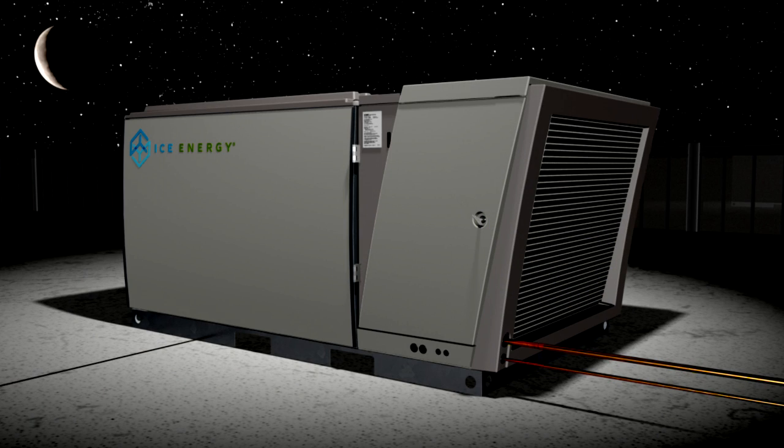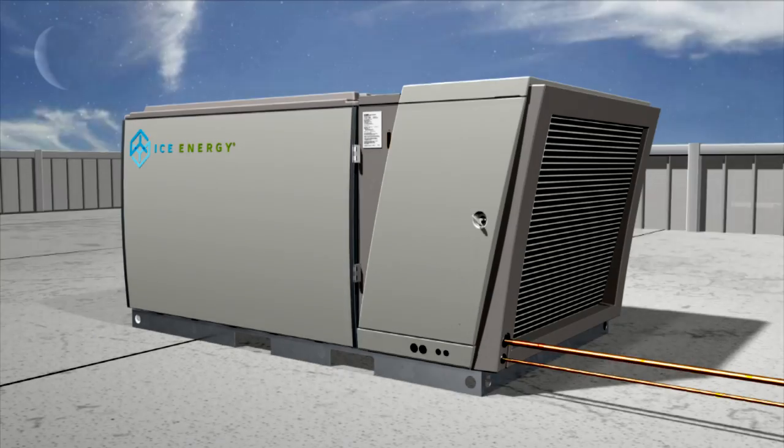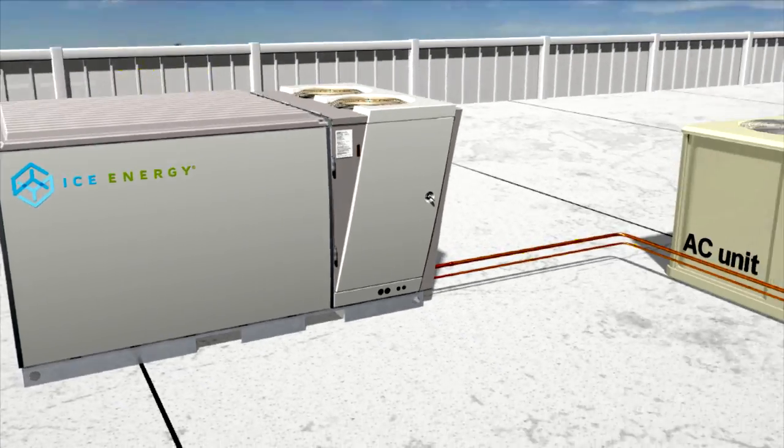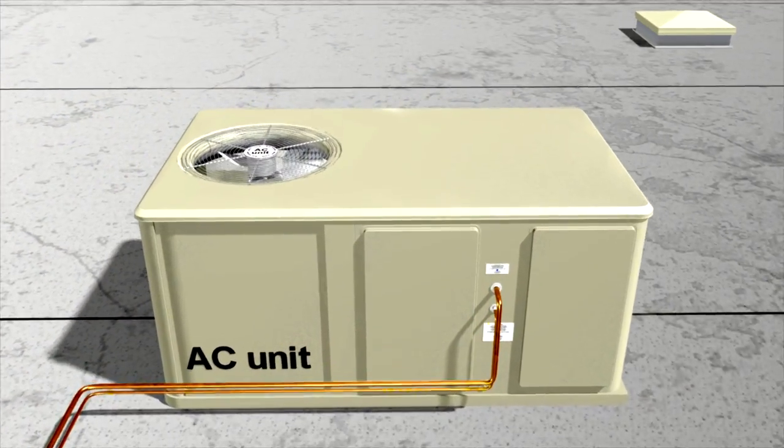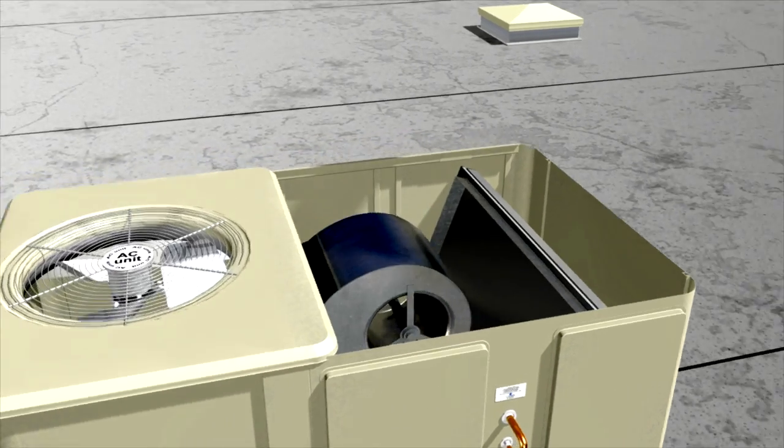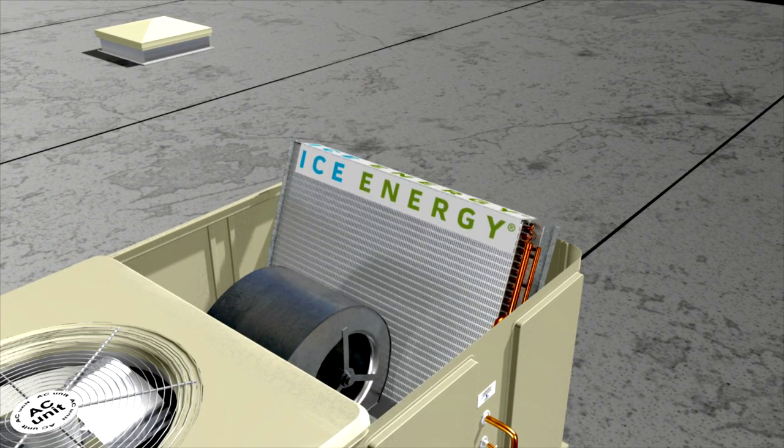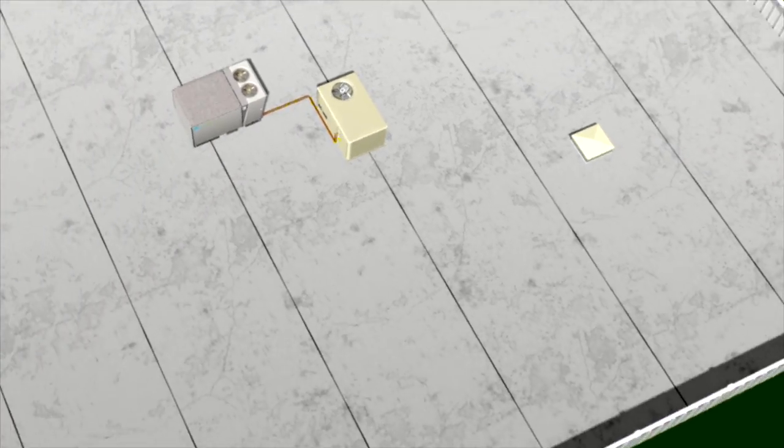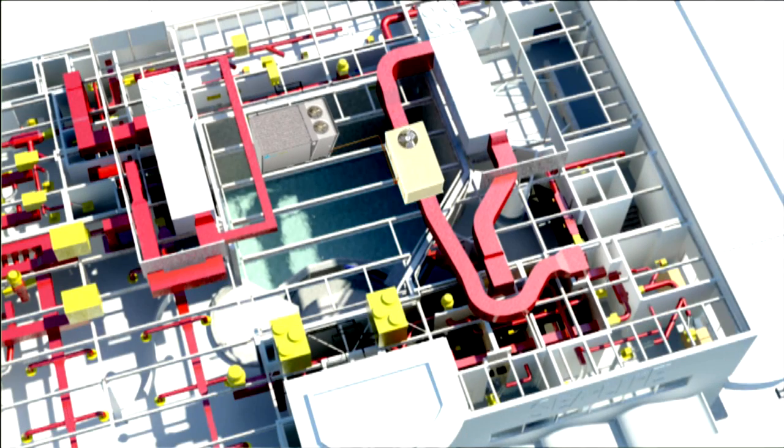Operation is simple and automatic. The IceBear stores energy at night and delivers that energy during the peak of the day. The IceBear integrates into the existing air conditioner by adding a new ice evaporator coil to the unit. No other changes are needed as the IceBear uses the existing air flow of the building's HVAC system.